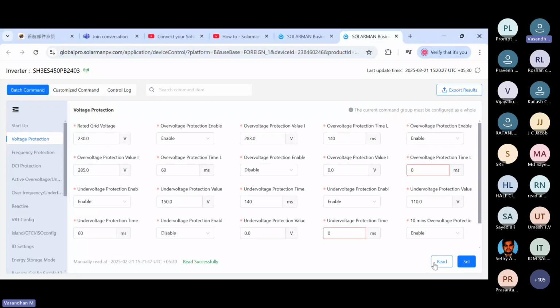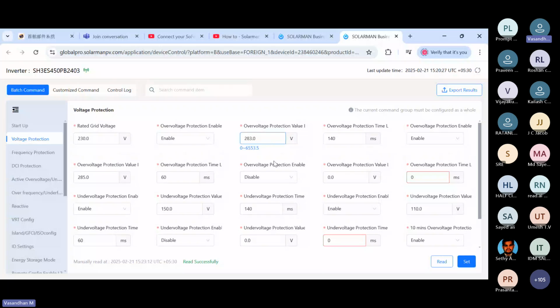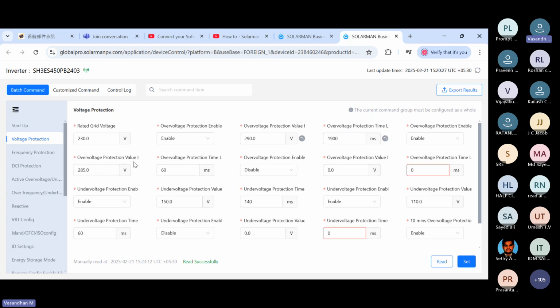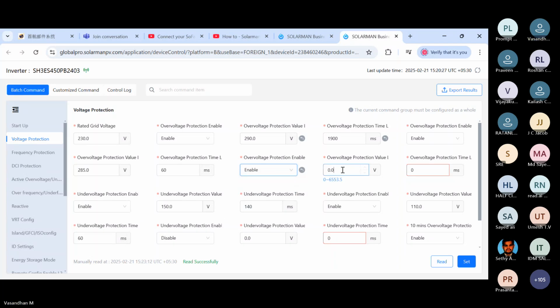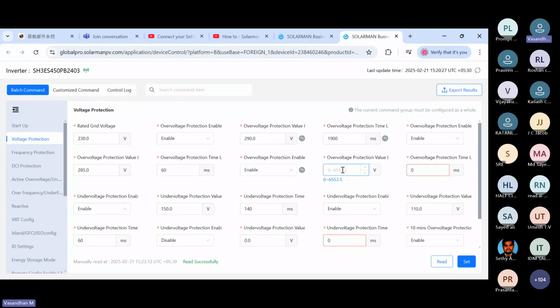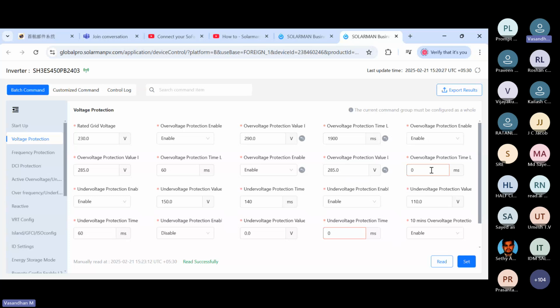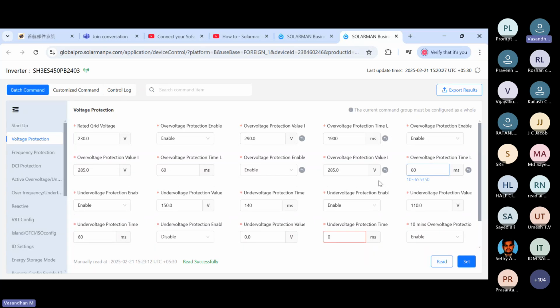We can read the file like this. It will show the values: rated grid voltage 230, over voltage protection value enable, and over voltage protection value 1. Here we can set 290 like that. Overall over voltage protection time 1900. These are all default values. So over voltage protection value level 2 is 285, and the second protection time is 60. This should be enabled. And over voltage protection value level 3 is 285. Like that we have to set. These are all set online.